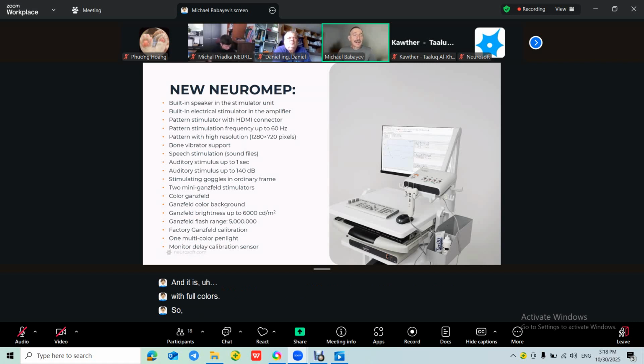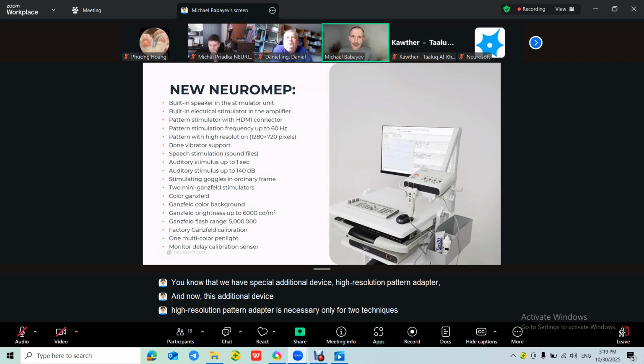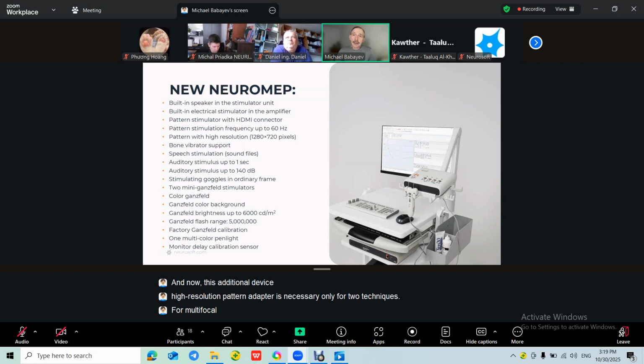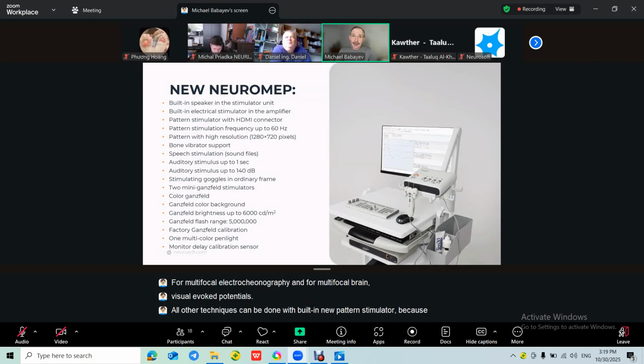So with this new pattern stimulator, it's possible to make, I think, most of the techniques without using the high resolution pattern adapter. You know that we have a special additional device, the high resolution pattern adapter. Now this additional device is necessary only for two techniques: for multifocal electroretinography and for multifocal visual evoked potentials. All other techniques can be done with the built-in new pattern stimulator because it has high resolution and full color.